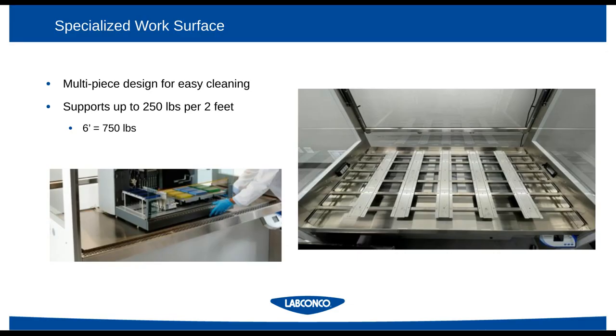I mentioned weight earlier, and that's another key factor, not only just for support of the instrument, but also ensuring that the enclosure does not flex or cause inaccuracies with movements like pipetting or other interfaces and integrations that are going to happen between liquid handlers and other instrumentation. So the robust nature of a work surface is really, although unseen, quite important to the operation of these systems. And so on our system, it's able to support up to 750 pounds on the 6-foot width, which is quite a clearance to allow for automated systems and all of the samples that are loaded onto them.